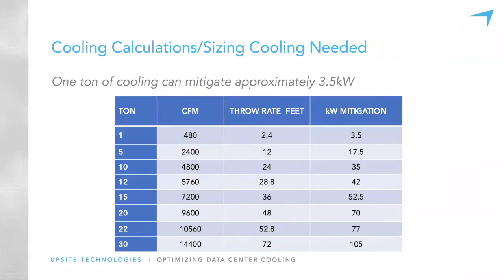I don't know that this is something I completely take credit for. This is a chart I've used for quite a long time, and as I travel, people find it incredibly valuable. It is not precise, but it is pretty close and more of a guideline for sizing the cooling needs within your data center. I break it down by tons, 1 ton all the way up to 30. We know that 1 ton will move roughly 480 cubic feet per minute, a throw rate, which means how far that air will travel and maintain the proper static pressure to allow proper stratification, 2.4 feet. And most important, the one I look at the most, I know 1 ton of cooling will mitigate 3.5 kilowatts of heat or power in a data center.